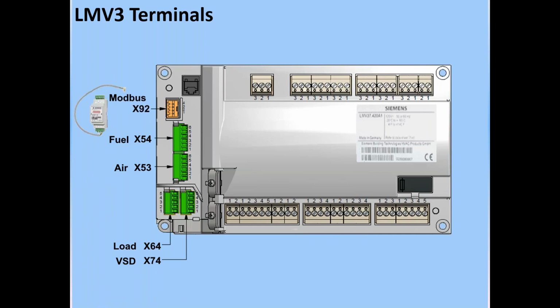Next, we have X92. That would be a Modbus port. You can take the OCI module with the supply cable and plug it into X92, and now you add Modbus feature to the LMV3. That would be for local touchscreens, BMS, lead lag systems, whatever you'd like for the Modbus features. Next, going around the LMV3, we have X56, which would be an RJ11 port. Typically, we plug in the AZL through the TDC combo wiring, or you can connect your personal computer to this and you can configure, backup, and restore the LMV3 or do trending.